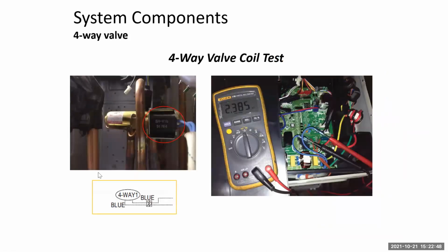And now we're looking at the 4-way valve or the reversing valve. These are high voltage. So when this unit's operating and heating, we have 230 volts AC going to them, or 115 volts, depending on your incoming voltage. If you're not reading the voltage and it's supposed to be there, or it's not within that range, then chances are your PCB board needs to be replaced.